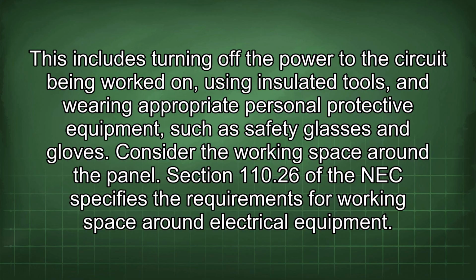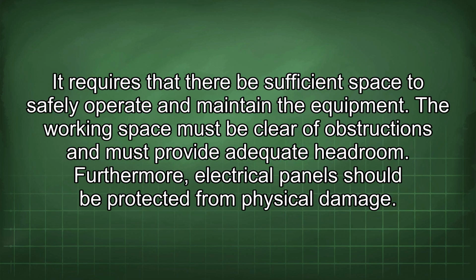Consider the working space around the panel. Section 110.26 of the NEC specifies the requirements for working space around electrical equipment. It requires that there be sufficient space to safely operate and maintain the equipment. The working space must be clear of obstructions and must provide adequate headroom.